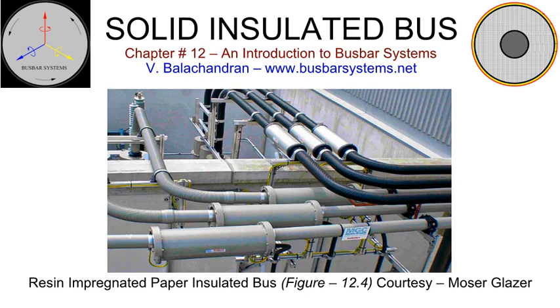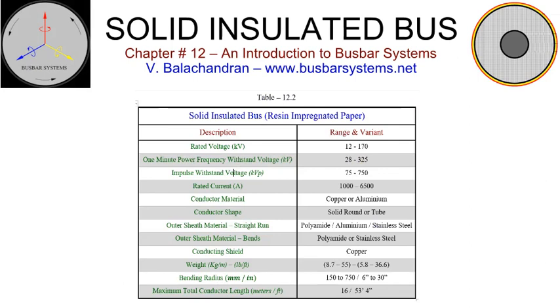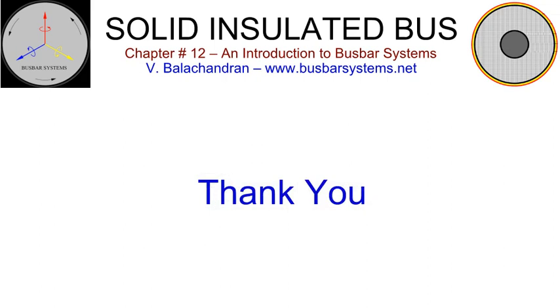These are customized supporting arrangements for indoor and outdoor installations. Fixed and sliding support blocks are manufactured to suit the product. Table 12.2 details the specification of solid insulated bus comprising rated voltage, kilovolts; 1-minute power frequency withstand voltage, kilovolts; impulse withstand voltage, kilovolts peak; rated current, amperes; conductor material; conductor shape; outer sheath material for straight run; outer sheath material for bends; conducting shield material; weight; bending radius; maximum total conductor length.